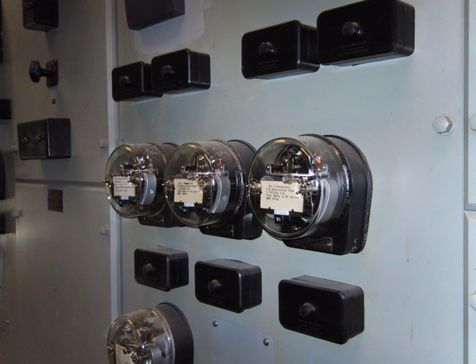Topic: Synchronism check. A synchronism checking relay provides a contact closure when the frequency and phase of two sources are similar to within some tolerance margin. A sync check relay is often applied where two power systems are interconnected, such as at a switchyard connecting two power grids, or at a generator circuit breaker to ensure the generator is synchronized to the system before connecting it.